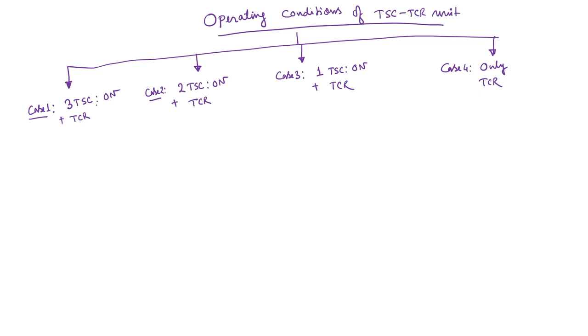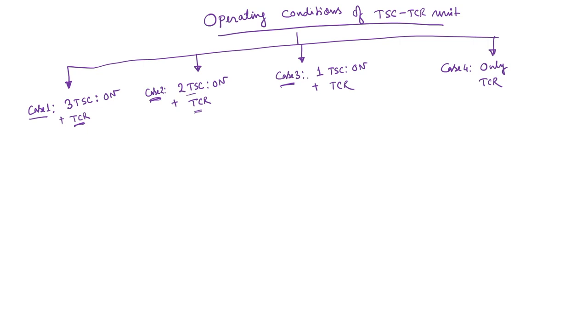So in Case 1, all the TSCs are turned on plus TCR will be in operation. Case 2: only 2 TSC units out of 3 will be turned on, meaning 1 TSC unit will be turned off, and the TCR will be operational. Case 3 will be only 1 TSC unit turned on along with the TCR unit, and Case 4 is when no TSC unit is turned on, meaning all TSC units are turned off, only the TCR unit is operational. During each of these cases, we will also get some sub-ranges of production and absorption. Now let us discuss this one by one.